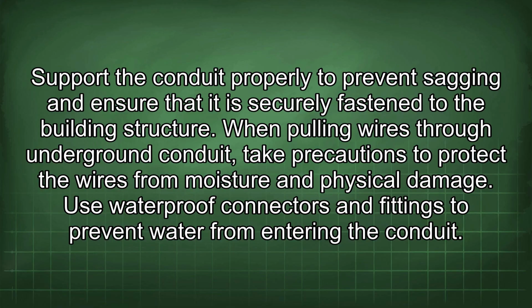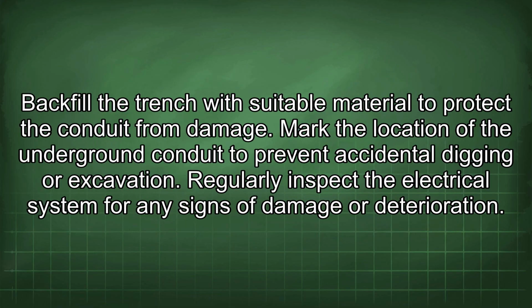When pulling wires through underground conduit, take precautions to protect the wires from moisture and physical damage. Use waterproof connectors and fittings to prevent water from entering the conduit. Backfill the trench with suitable material to protect the conduit from damage. Mark the location of the underground conduit to prevent accidental digging or excavation.